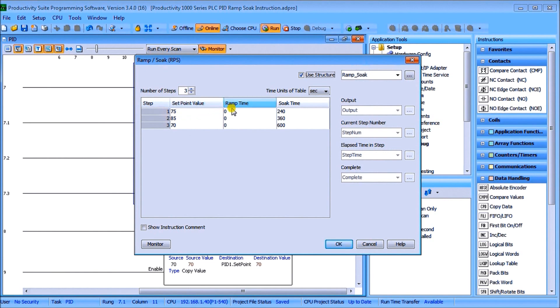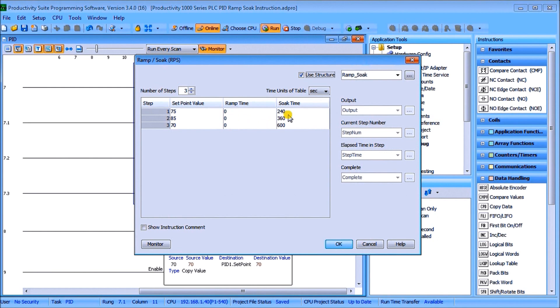The ramp time is the gradual increase that we want. Now in our case here we're going to leave that zero and we're going to allow that to ramp up as quickly as possible based on our PID parameters. Then what we do is we're going to put a 240 second soak time to keep that temperature at the same.